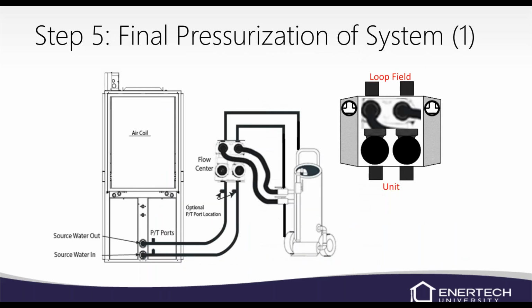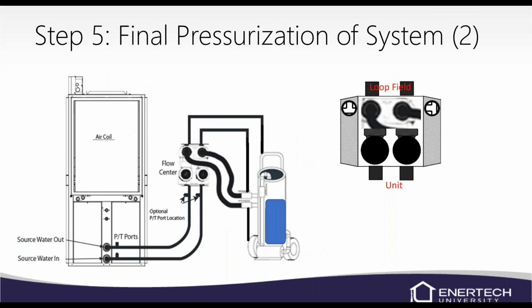Then after you've got your antifreeze mixed and you've got the right amount in the system, we'll do our pressurization, which is pretty simple if you've got a flush cart. Basically, you're going to close off one of the valves and deadhead that pump back to the flush cart and build pressure. Make sure you've got a pressure gauge in your PT port, because we don't want to get too much pressure in there.